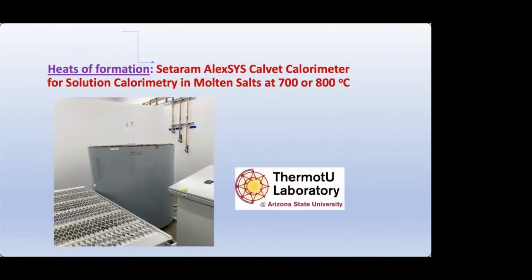The calorimeter itself, and this is our new calorimeter here at ASU, is based on calorimeters that we have built in our laboratories, but now it is commercialized as the Setaram Alexsys calorimeter for solution calorimetry in molten salts and other applications. And a number of groups in the United States, Europe, and elsewhere have now bought these calorimeters, and I'm proud to say that they are getting independent of me in planning and doing experiments.